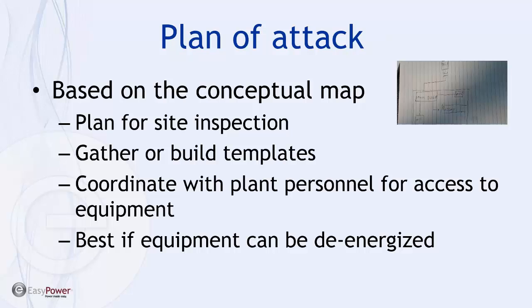Based upon the plan of attack, even if you start with a hand-drawn one-line diagram, you need to build up a plan for site inspection. One of the more costly elements of doing an arc flash hazard assessment is the data collection phase. Because if you don't do a good job at the first pass, you will continually have to go back and recollect data. So as you understand what needs to be collected, you need to build templates for that. I will recommend some reference material available from the website that can be utilized.